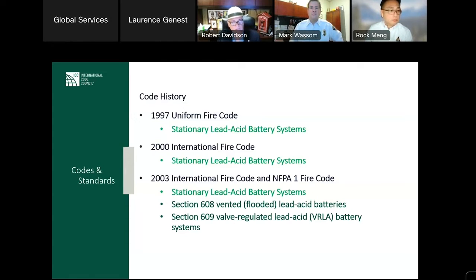application started in 1997, where we carved out stationary lead acid battery systems. And really, we carved them out to eliminate treating them as a hazardous material installation because of the amount of electrolytes. We created a special place for them. In 2000, the legacy codes in the United States merged, and that language moved its way into the International Fire Code. In 2003, it moved its way into NFPA 1 Fire Code, and we added a new section that had to do with valve regulated. So we had a section on vented lead acid, a section on valve regulated, extremely similar.